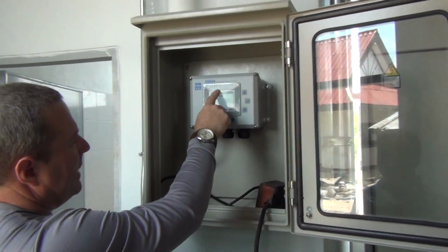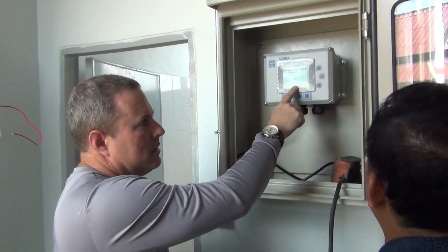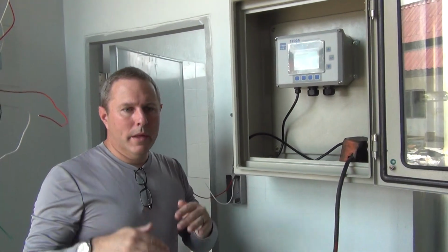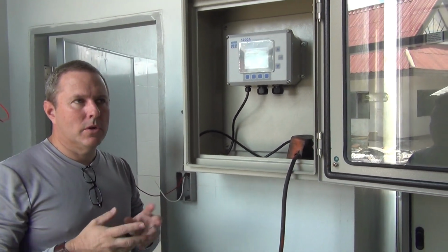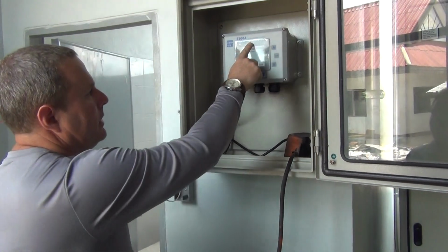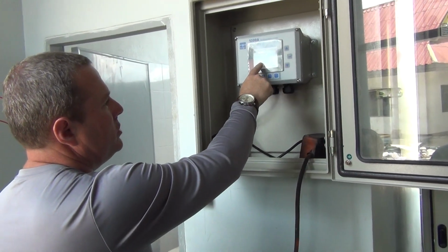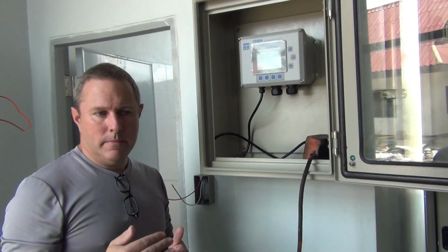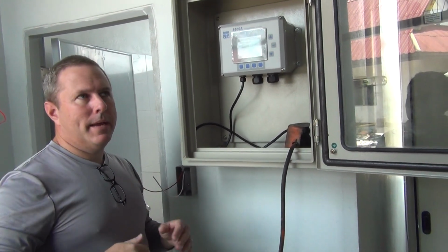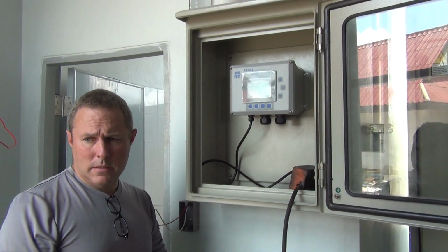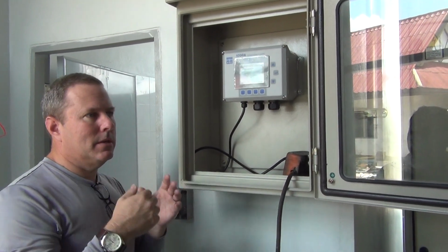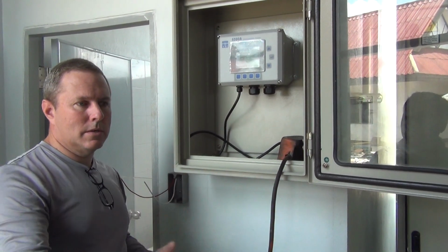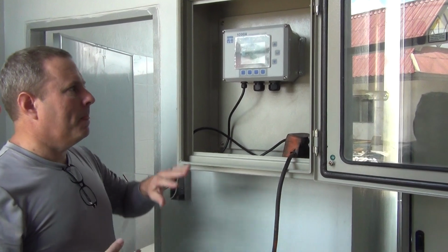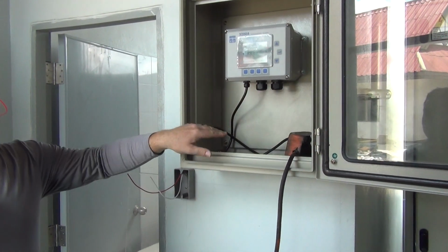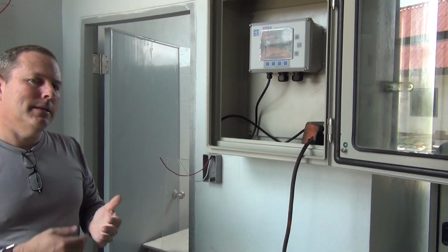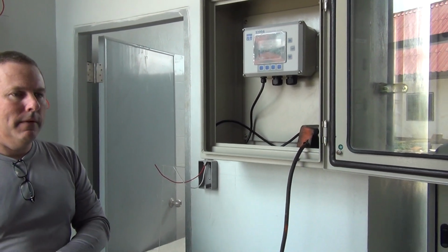Okay. We will have to set the set points here. So I think what we need to do is find out what the exact levels we turn on and turn off at. Because what we will be doing is we will set a low range, a high range, and a set point. Then, if it gets beyond those, we can set alarm points. An alarm point can be used to trigger a second device to notify someone that it has gone outside of range. So if we connect the unit to the internet, we can also have it send email messages or text messages to notify people if there is a problem.